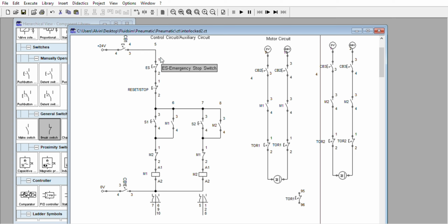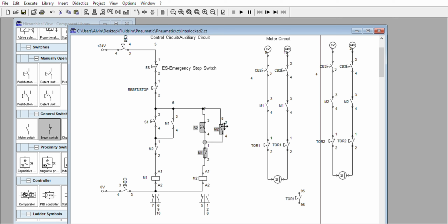Okay, if we are going to use the thermal overload relay, since there are two motors, we are going to put the thermal overload relay in series here. It should be a dominant stop, in series here or in series at the top. There are two possible connections. It depends on how you're going to present. The best way is near the coil. You have the standard that is usually at the top of the coil, at the top of the push button. Some prefer this way, as they can see immediately the connection during troubleshooting. You can also have this one.